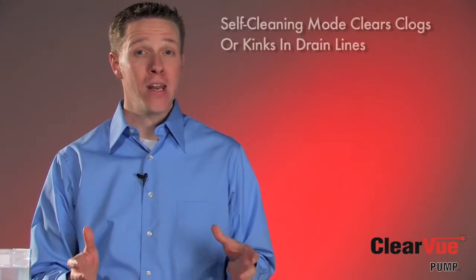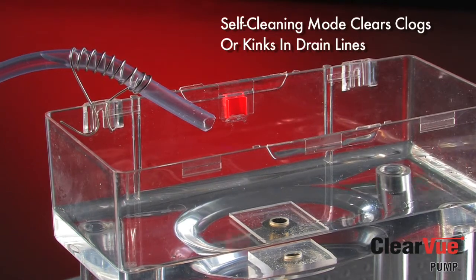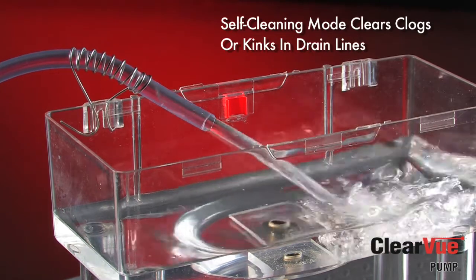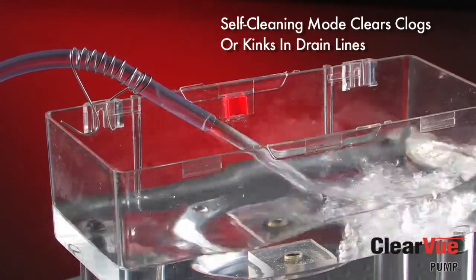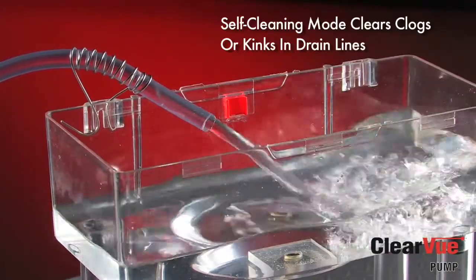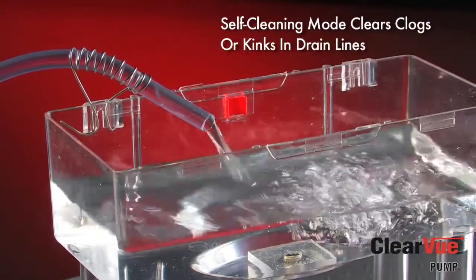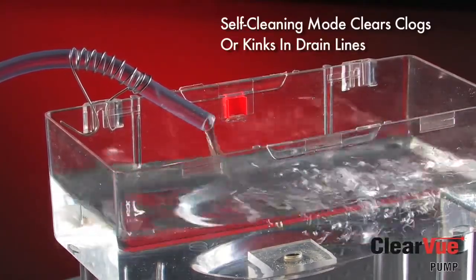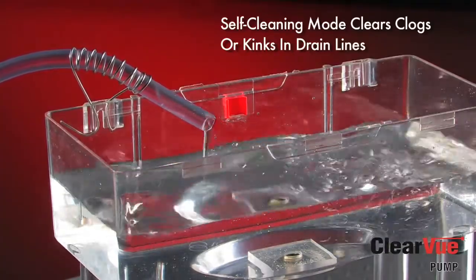Another thing that's happening in alarm condition is that after about a minute of pumping at full speed, ClearVue will go into what we call our self-cleaning mode. What the self-cleaning cycle is going to do is use the water in the tank to send pressure pulses through the line to try to dislodge any clogs or kinks that might have formed. ClearVue has determined that there is a problem and is working to clear the clog and return to normal operation. The pump is trying to get out of that alarm state without a service call or a contractor callback. ClearVue is the only pump that fixes itself when it senses a problem.